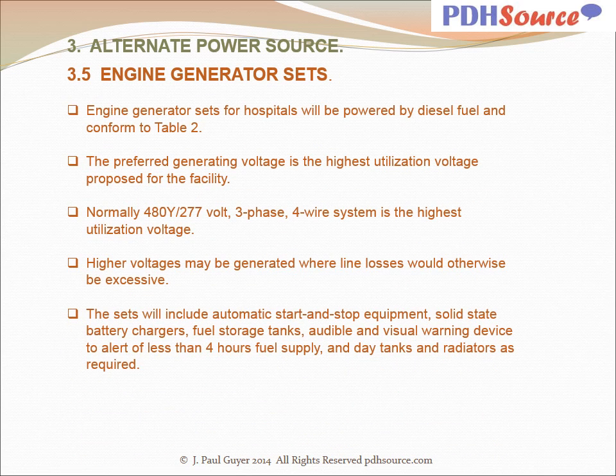With regard to the engine generator sets, for hospitals they will be powered by diesel fuel and conform to Table 2. The preferred generating voltage is the highest utilization voltage proposed for the facility. Normally, 480Y/277 volt three-phase four-wire system is the highest utilization voltage. Higher voltages may be generated where line losses would otherwise be excessive. The sets will include automatic start and stop equipment, solid-state battery chargers, fuel storage tanks, audible and visual warning devices to alert of less than 4 hours fuel supply, and day tanks and radiators as required.